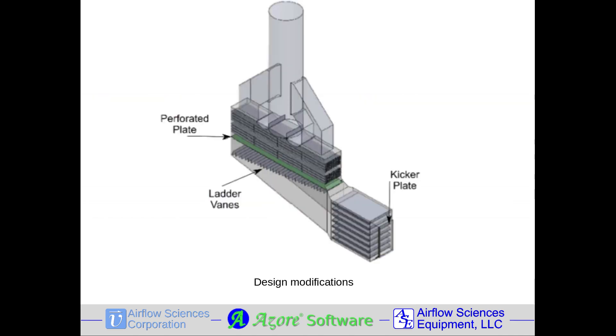The CFD modeling design effort included an iterative approach to develop an arrangement of flow control devices, including a perforated plate, ladder vanes, a series of kicker plates, as well as minor modifications to the layout of the silencer baffles.